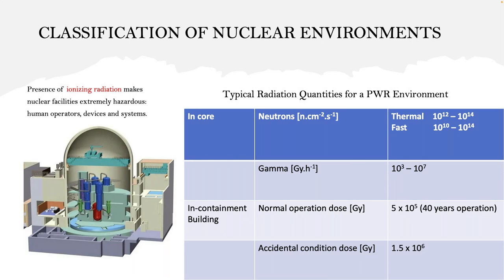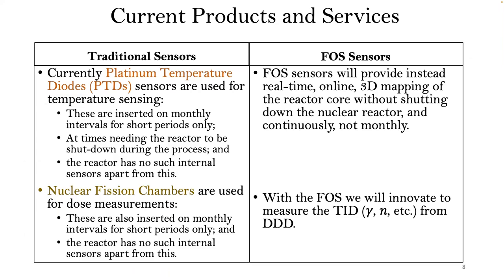Hence, we want to apply the fibers. Even outside the core in the containment building, the environment is still very harsh. Normal operation dose there can pick up to about 10^5 over a period of 40 years of operation. Under accidental conditions, your dose can pick up to the megagray range, which is quite deadly for electronic components. So the question is: what do we currently have in the nuclear reactors compared to what we want to provide with fiber optic sensors?